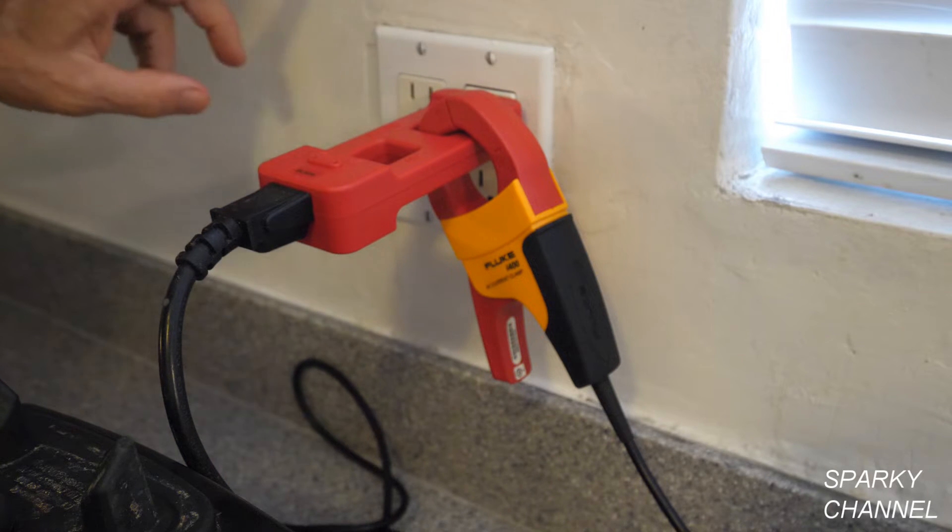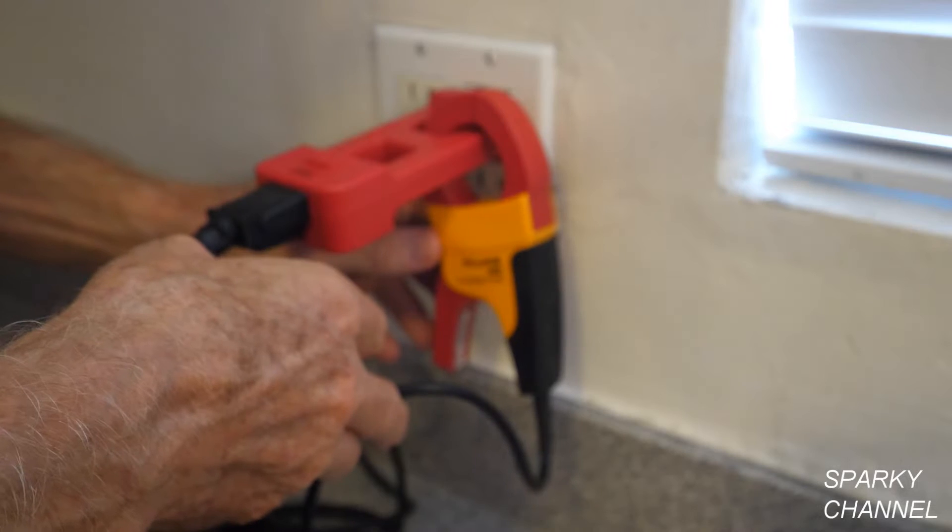And you should know that with a 20 amp circuit you shouldn't exceed 80% of its capacity. So that would be 16 amps out of the 20 amps. You don't want to be going 17, 18 amps. Even though it doesn't blow the circuit that's more than is advised.